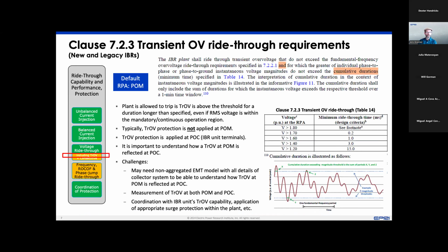But really the takeaway here is that the transient overvoltage ride-through requirement is a plant level requirement. So the plant is allowed to trip based on transient overvoltage if the transient overvoltage is above the specified thresholds for a certain duration or longer, even if the RMS voltage is within the mandatory or continuous operation region. So it's all about the time frame.